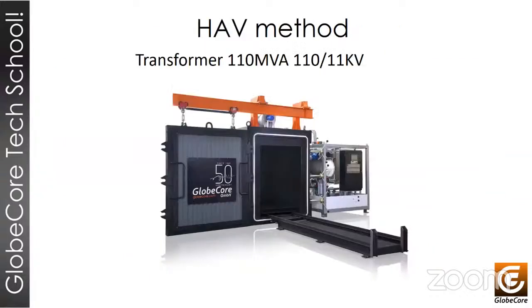The first method we are going to consider is HAV. As we already said before, the drying process involves cyclic heating plus vacuuming, with a subsequent increase in temperature and rise of vacuum level inside the chamber. The heating process uses the power supply to ensure the operation of heating plates inside the chamber, as well as the drive for circulation fans. After that, the heating system is disengaged and the vacuum unit is engaged, which requires power for the vacuum pumps and the cooling system. This procedure is repeated for a certain number of cycles based on the drying technology.